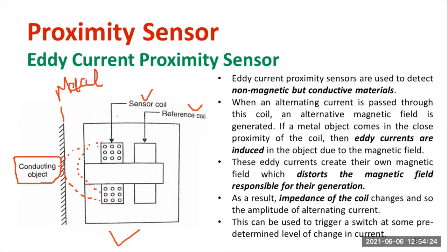Due to the induced EMF generated in the metal part, there will be a formulation of continuous circulating current flowing through the metal part — this is called eddy current. The presence of eddy current is identified in the metal object. Because of the eddy current passing through the metal part, it will distort the main magnetic field produced by the sensor coil. At that point, the impedance of the sensor coil varies. By connecting the changes in impedance to a switch, the switch operates according to those impedance changes.